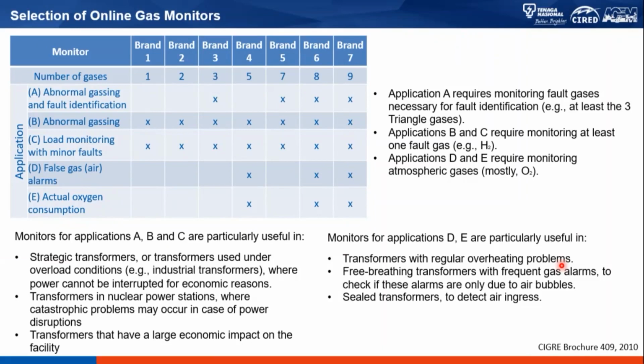In the CIRED report, referring again to the previous CIGRE brochure 409, 2010, it gives some guidelines on the application of online gas monitors. Are you looking for A, abnormal gassing and fault identification? B, abnormal gassing? Or are you looking for load monitoring with minor faults, false gas alarms, or E, actual oxygen consumption?